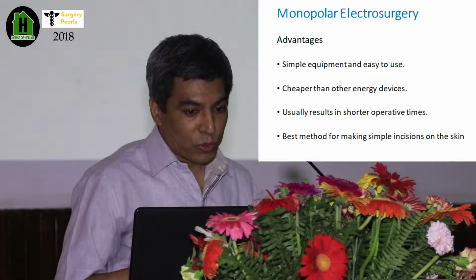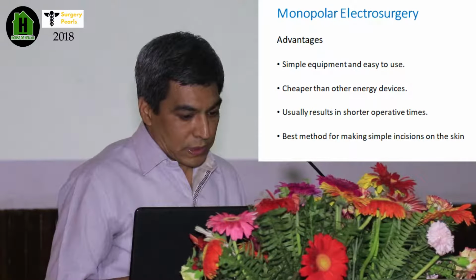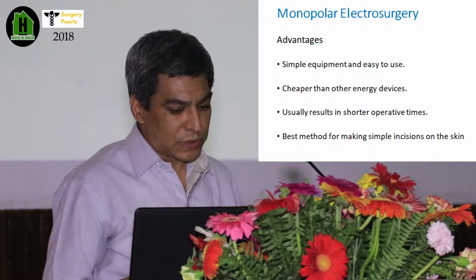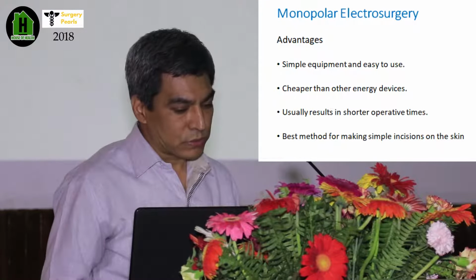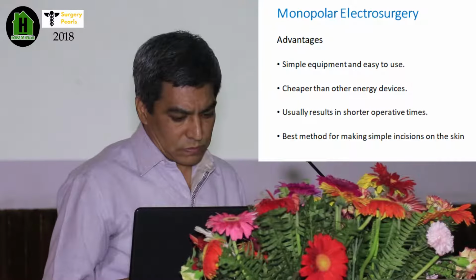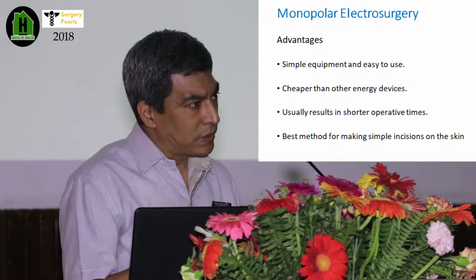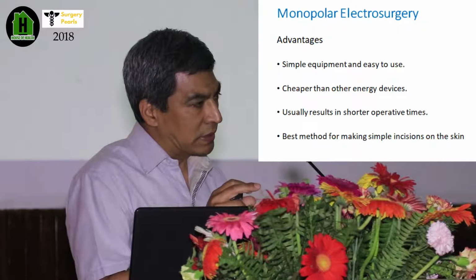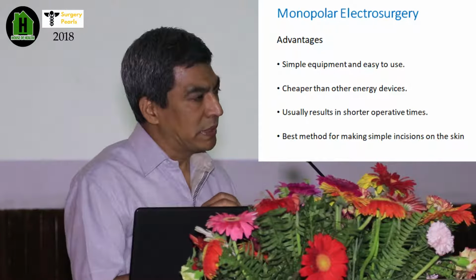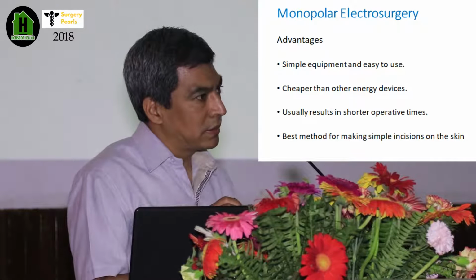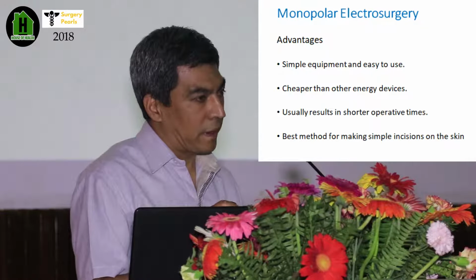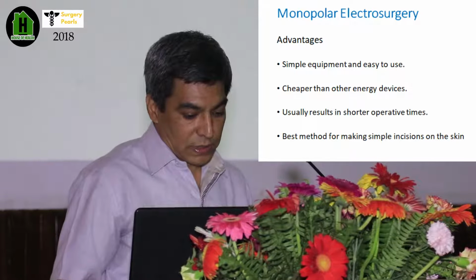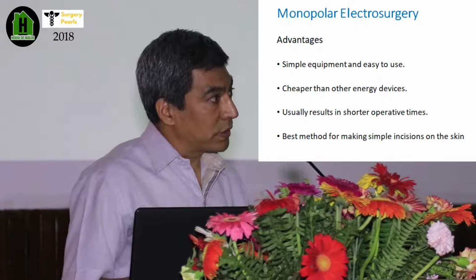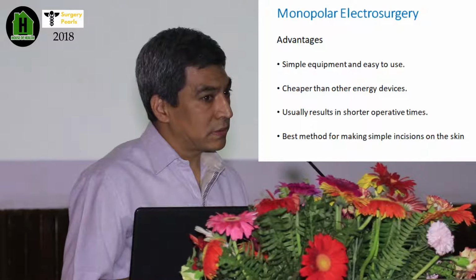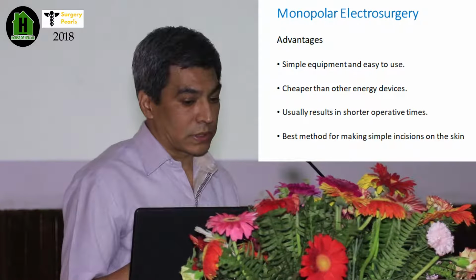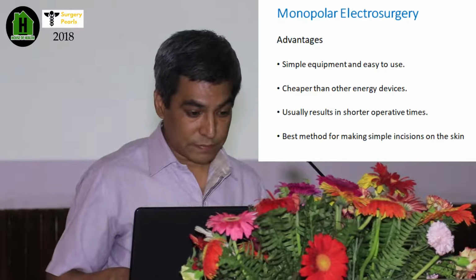So what are the advantages of monopolar electrosurgery? It is very simple equipment. Everybody can use it. And it's cheap, it's the cheapest I should say. The operating time is very short because it can produce heat immediately, more than desired. So operating time itself is very short, unlike other devices. We'll come to that. And for skin incision, this is the best device. If you have to do a skin incision with electrosurgical units, then this is the best device for that.